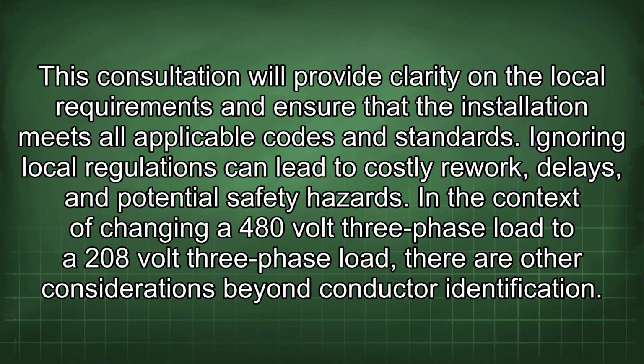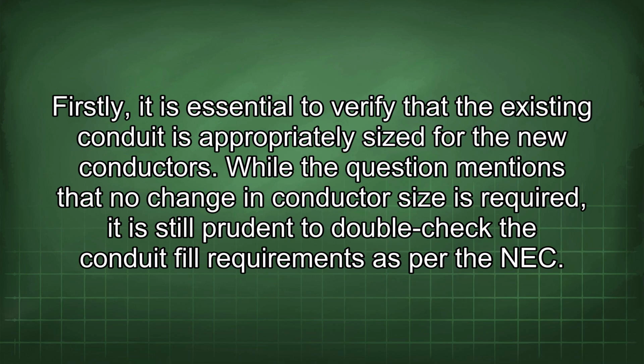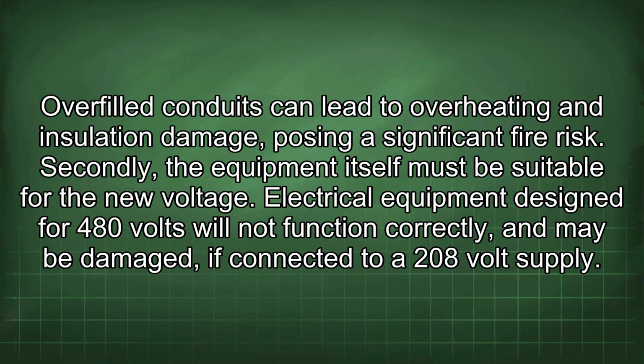In the context of changing a 480-volt three-phase load to a 208-volt three-phase load, there are other considerations beyond conductor identification. Firstly, it is essential to verify that the existing conduit is appropriately sized for the new conductors. While the question mentions that no change in conductor size is required, it is still prudent to double-check the conduit fill requirements as per the NEC. Overfilled conduits can lead to overheating and insulation damage, posing a significant fire risk.